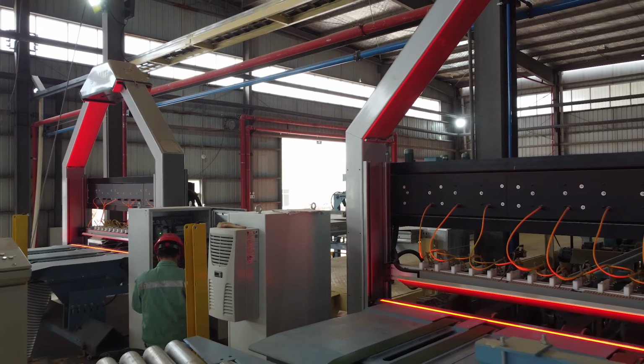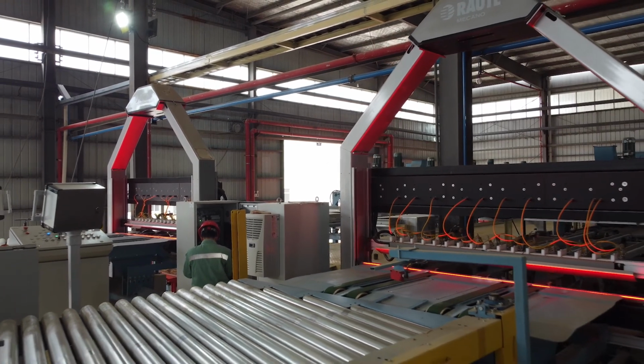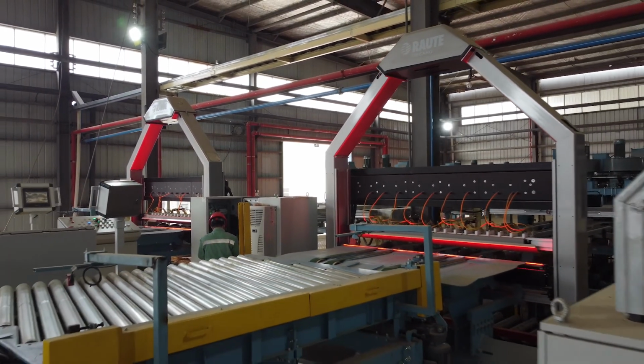If you have very basic cubics in, cubics out, uptime from the production, that won't help. There are a couple more steps that you need in between. First one is, of course, you need the product dimensions. That alone tells a lot when you look at condition monitoring data. In addition, we can have from the HMI panels all the parameters that are in use. If there are some offsets in use, speed increased or pressures decreased, all those also have an effect on the sensor data in the condition monitoring. In addition, we can apply the grading data, which gives you filters enough so that you can make sense also of the condition monitoring data.